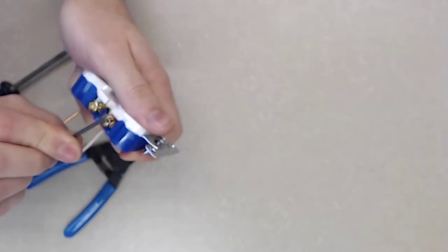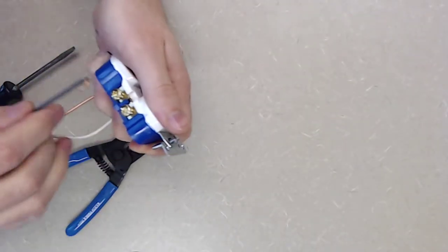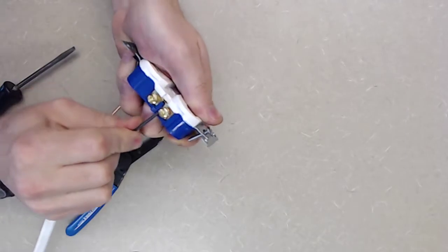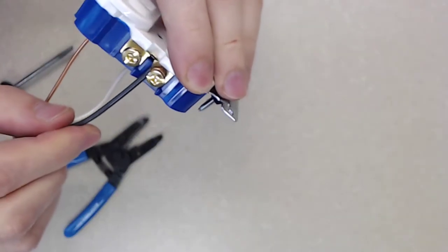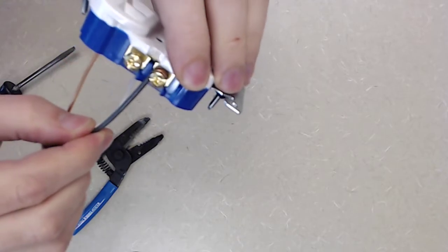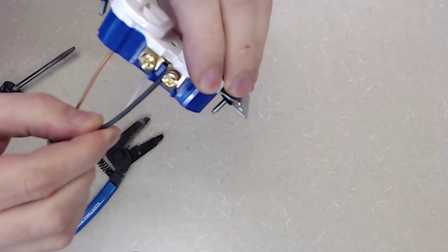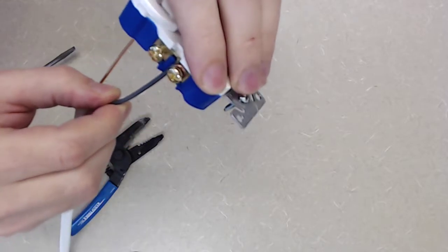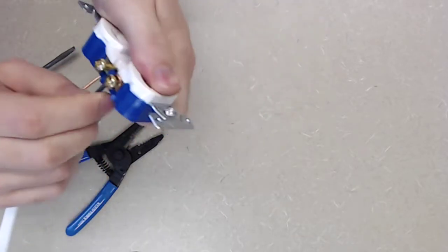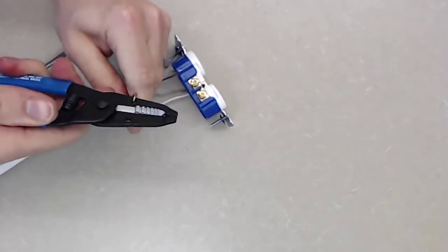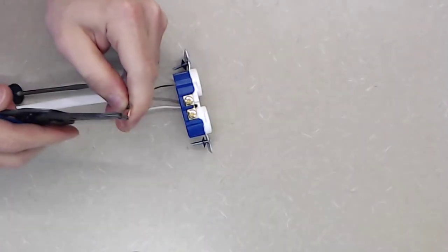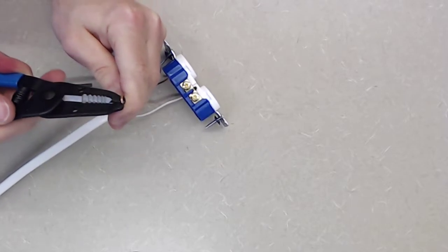Same with the other side. Now, this is going to be more of an issue, so you see where I'm actually underneath the screw with the insulation. I would want to actually re-bend that, so that that insulation is not impeding the connection between the copper of the wire and the copper or the brass of the actual screw.